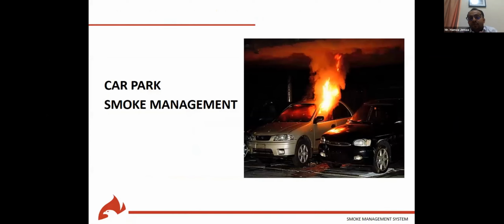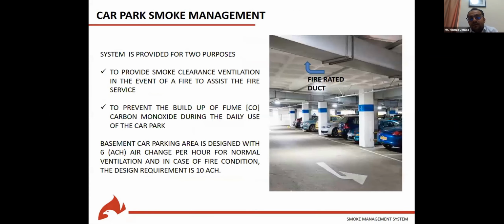Another application of smoke control system is for car park systems. Using smoke control system in car parks is very important even in normal cases, to prevent the buildup of CO gas in daily use. And there is a well-defined sequence of operation controlling the percentage of ppm at which the extraction fan should work in normal mode, at 6 air changes per hour, and in case of fire, it will run at a higher mode, at 10 air changes per hour.